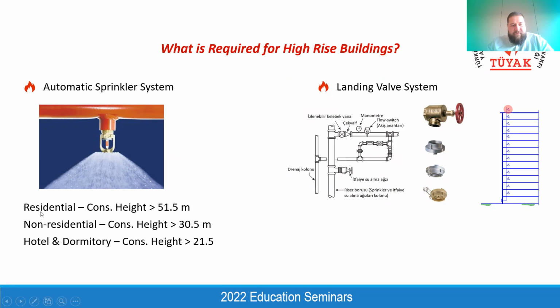But for the high-rise building, for a residential building, if the construction height exceeds 51.5 meters, or for a non-residential building, if the construction height exceeds 30.5 meters, the automatic sprinkler system becomes mandatory. And informing the mechanical designer about construction heights is the responsibility of the architect. For example, some investors of residential buildings limit the construction height to 51 meters in order not to provide a sprinkler system. They limit their height to cut expenses during the construction phase.